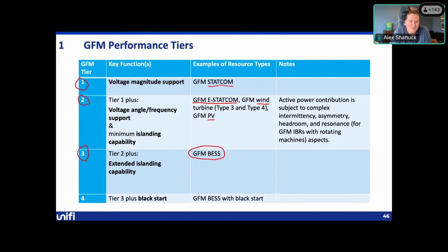Headroom would most often have to be driven by a market mechanism or an actual mandatory enforceable standard, because asking the owner of an IBR plant to willingly lose money on selling power is something we haven't gotten around to in the discussions. It could be very difficult or sometimes impossible to actually get headroom in the real world without a bunch of procedural and regulatory changes. So that was just my 2 cents on headroom.